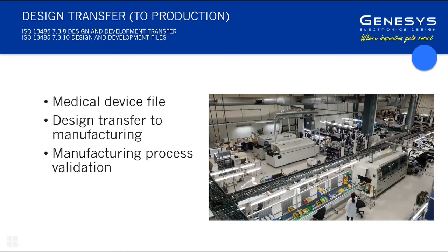And it's also important to consider there are two pathways to validation. If you can verify the outputs of the process, you don't necessarily need to fully validate the process. But if you can't verify the outputs, you must validate the process. Good example is sterilisation, where you can't test every single unit to prove it's sterile because you have to breach the sterile barrier to make sure it's sterile. So you can't do that.